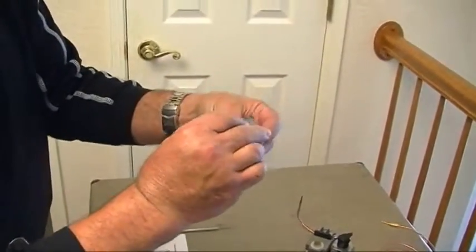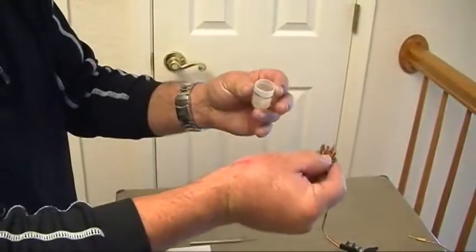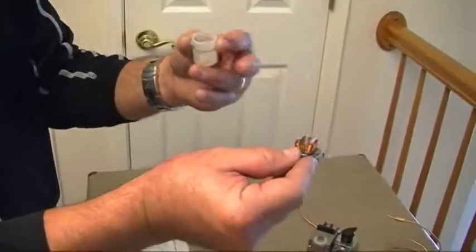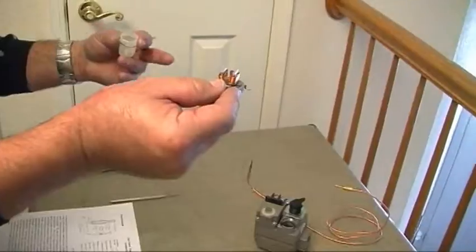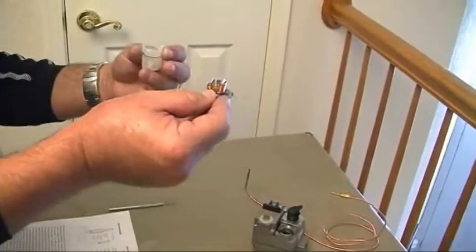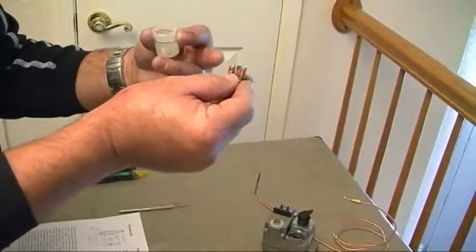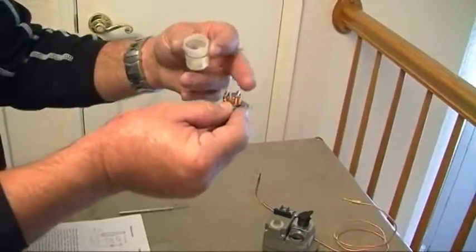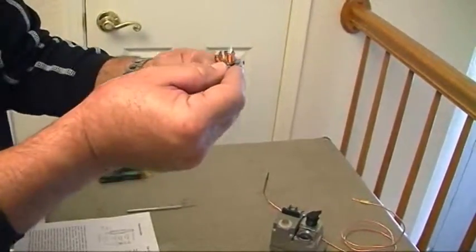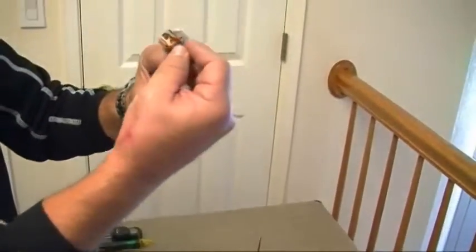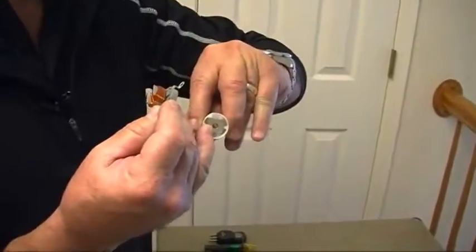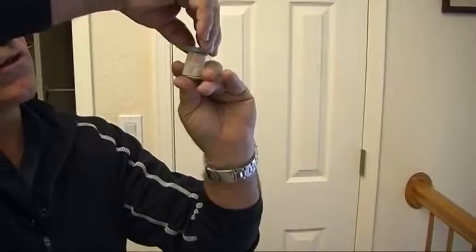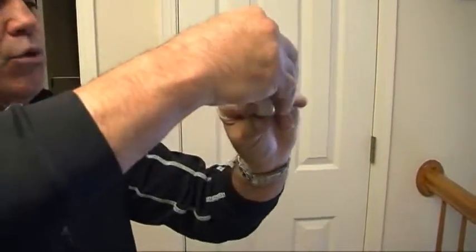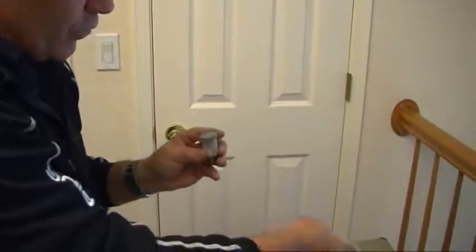So we're going to take off this section here, and we're going to look at the windings around these two steel posts. When the millivolts come through your thermocouple and go through here, they magnetize these two steel posts, which pulls in the mainspring, and this is what's called the keeper. The keeper gets attached to it. So it looks somewhat like that. I don't know if you can see it through that clear section, but it pulls that up, allows the gas to flow through the pilot.